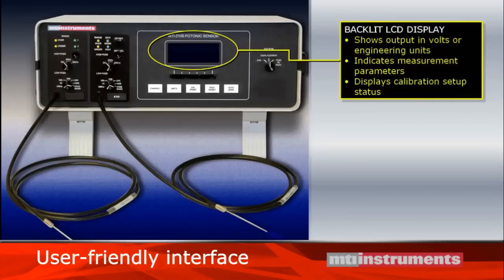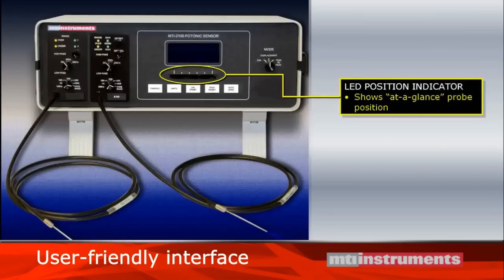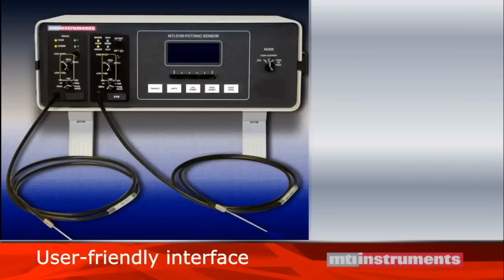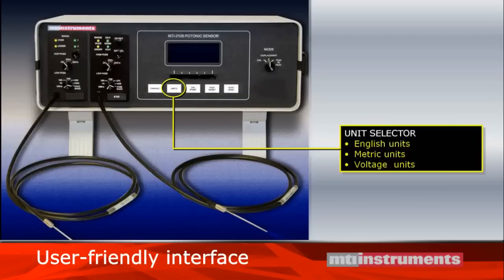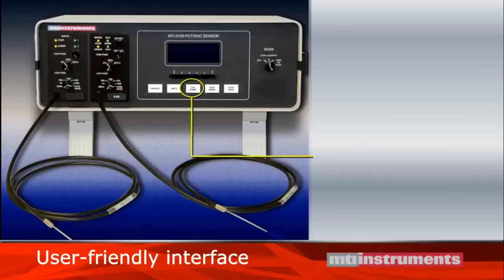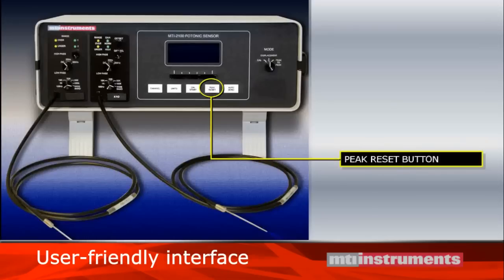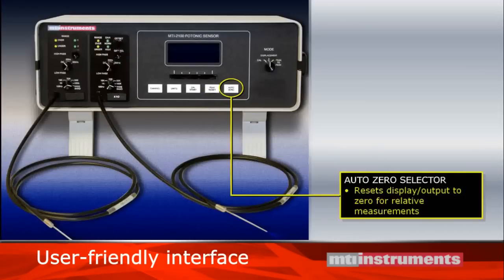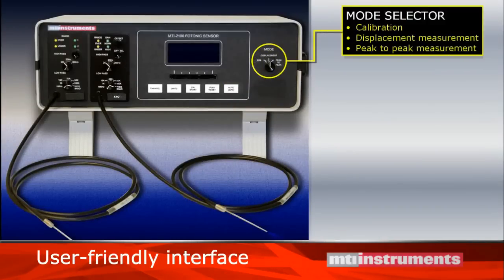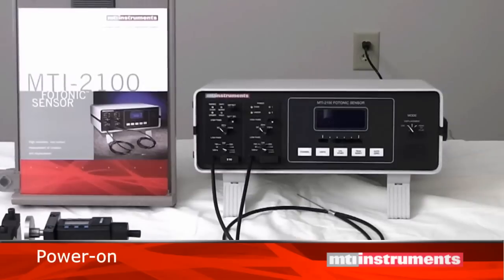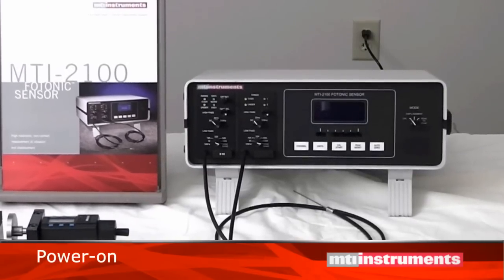We have a backlit display, an LED bar graph indicator which shows probe position, a channel selector switch, unit switch for English, metric, or voltage, a calibration start button. Peak reset button allows you to instantly bleed off any unwanted spikes or transients on the peak-to-peak output signal. Auto zero button, which acts like a tare function for the digital display. Mode selector switch enables you to switch the MTI 2100 controller display from displacement mode, peak-to-peak vibration mode, or to the calibration mode. Next, we power on the MTI 2100 photonic sensor.